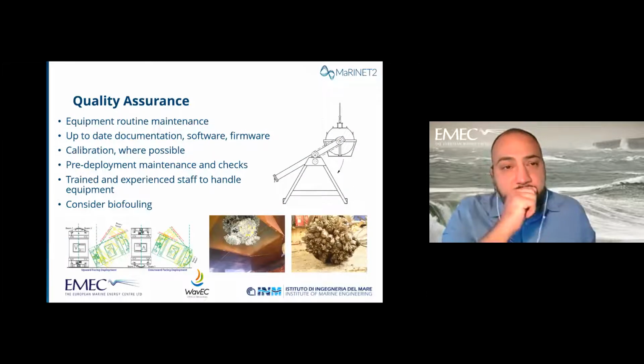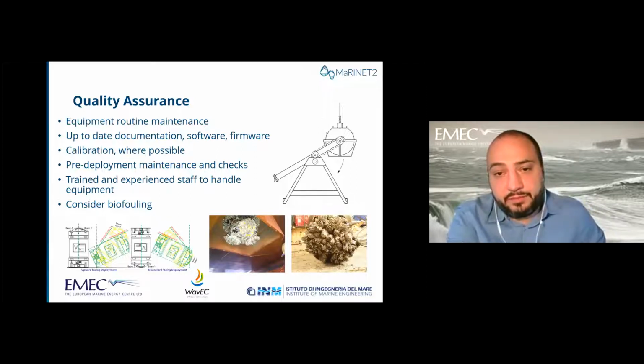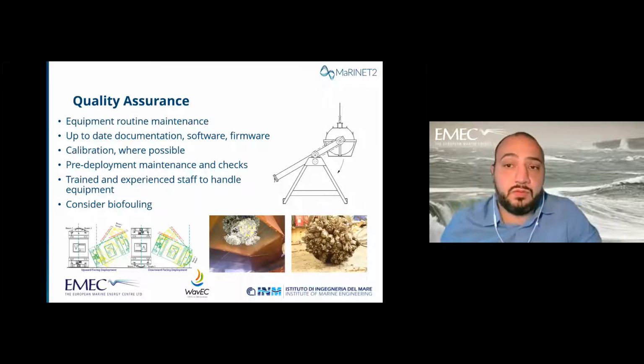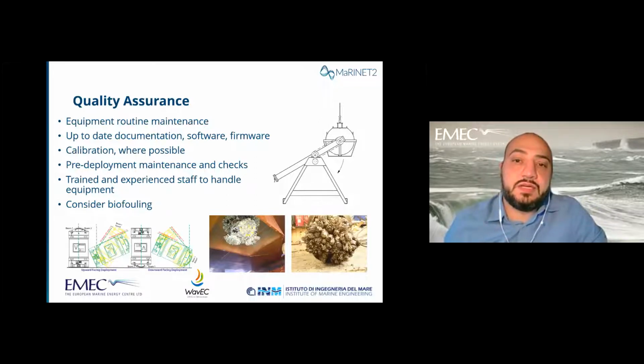A few more steps: the equipment needs to be routinely maintained. That's good practice, and in our case it's also a requirement that we have a schedule to look out at the equipment, change the O-rings, add or change some parts, bits and pieces of the instruments. All the documentation, software and firmware have to be up to date, since bugs are often discovered and manufacturers sort them out through software or firmware updates.